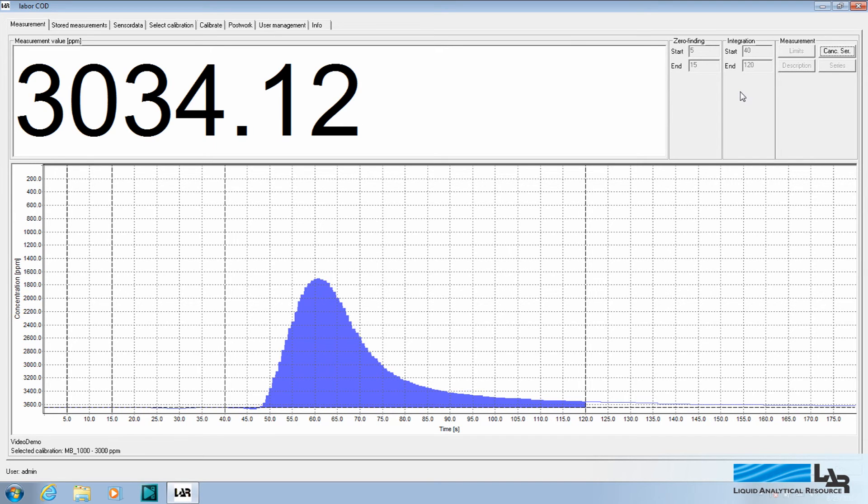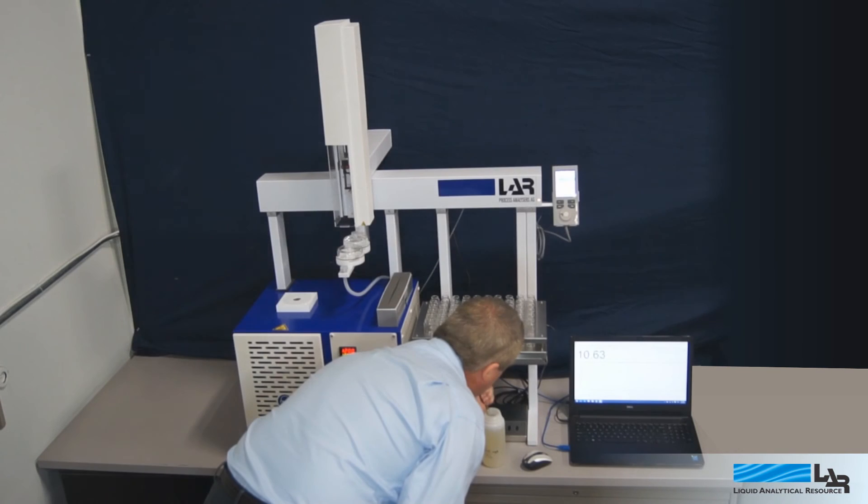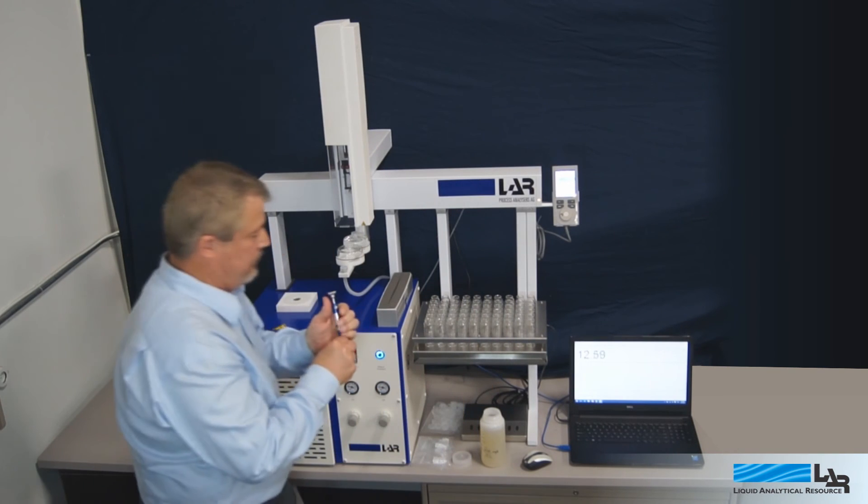With the sample now consumed, the oxygen level returns to the baseline, and the system is ready to perform another measurement.